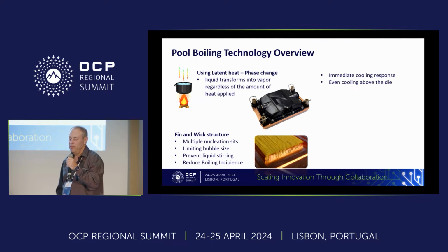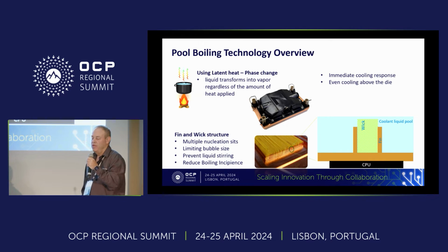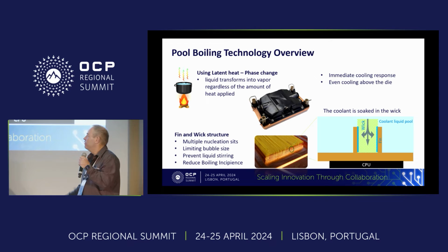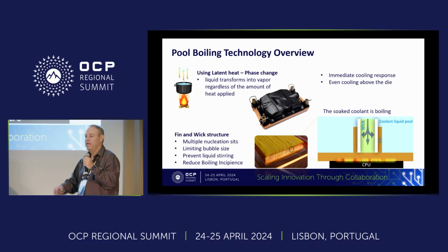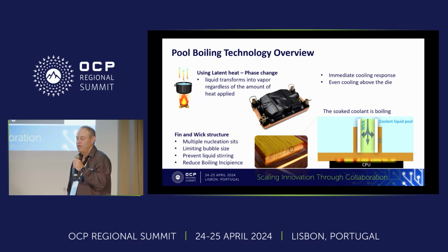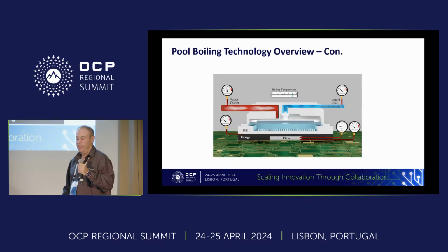It's called pool boiling, and the structure of fins and wick that you see here provides a solution that creates very, very efficient boiling without any bubbles on the surface, without any hot spots. There is a wick material, like a sponge, between the fins inside the cold plate. That wick material is saturated by the liquid that is being boiled, and the boiling happens between that saturated liquid and the fins, creating very efficient boiling with very small bubbles and preventing bubbles on the surface. That was the problem with evaporators, the reason why they were not used to cool chips, and that's what ZutaCore actually succeeded in creating: efficient boiling in an evaporator.